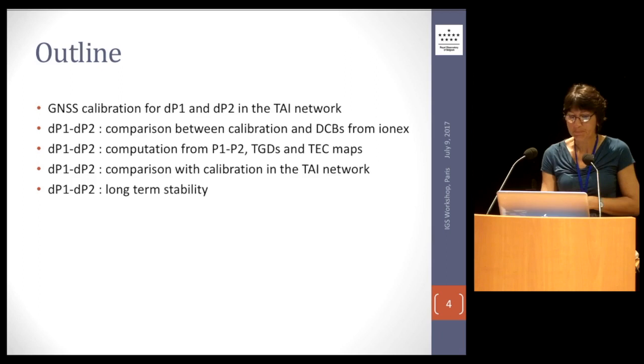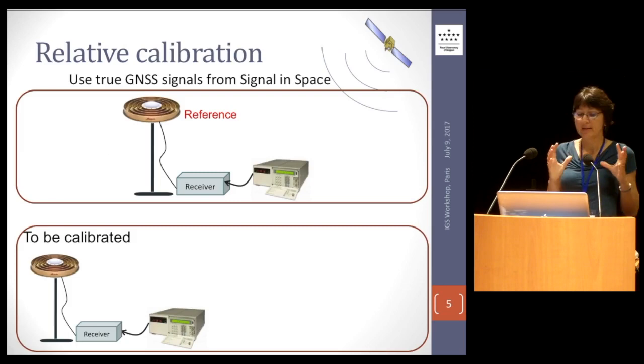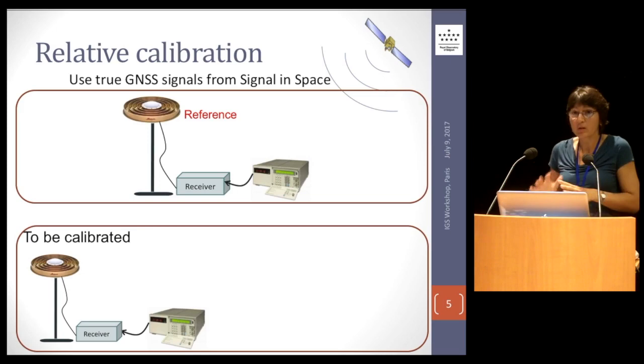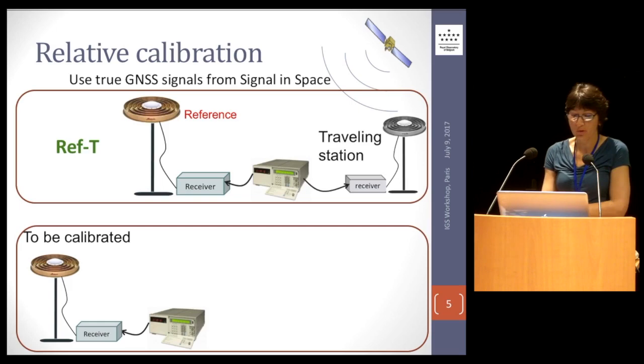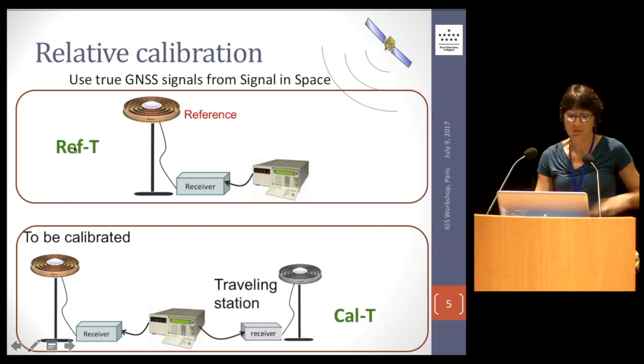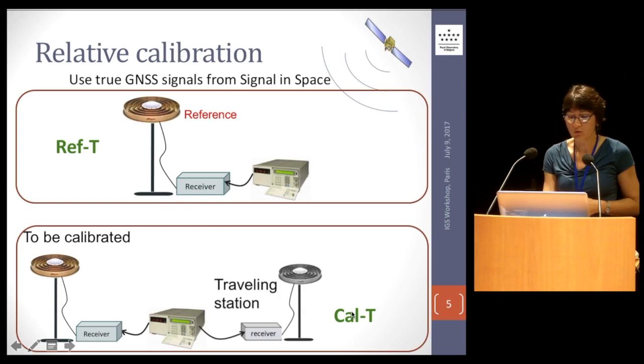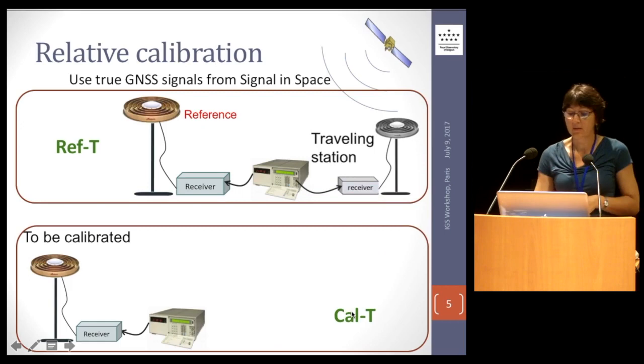In the TAI community, we have one reference which has in fact been calibrated absolutely using a simulator, but about ten years ago. We maintain this reference in several locations. From a reference, we use a traveling station that we compare first to the reference, so we have the difference between the hardware delay of the traveling station with respect to the reference. Then we move the traveling station to the different stations to be calibrated, where we have the difference of hardware delay between the traveling and the station to be calibrated. Then to make a closure, we go back to the reference to verify stability in the traveling equipment.